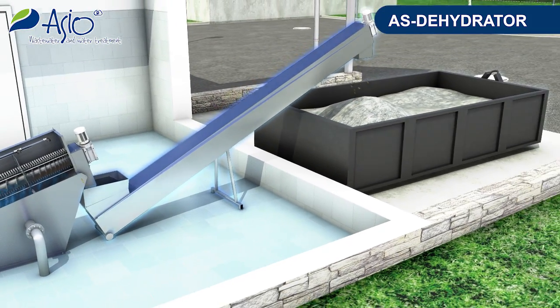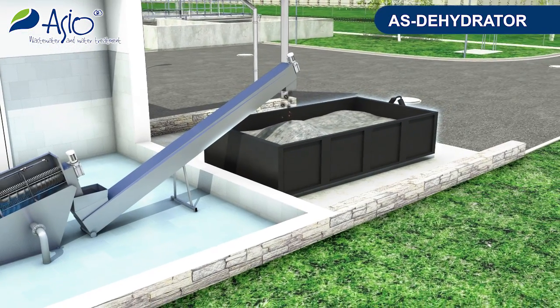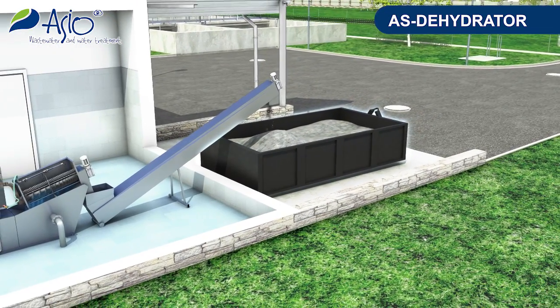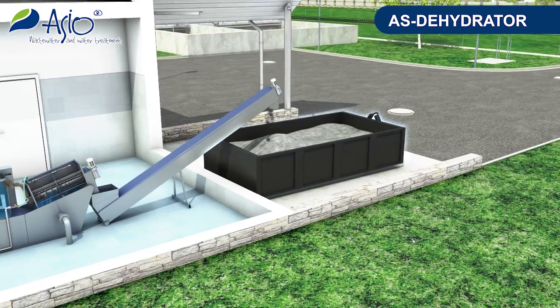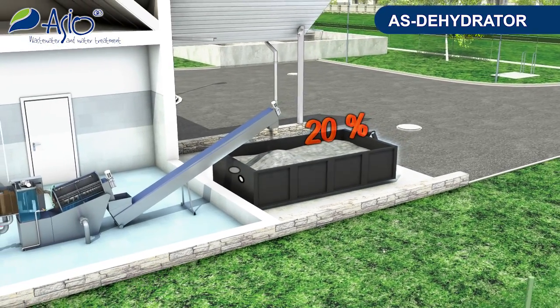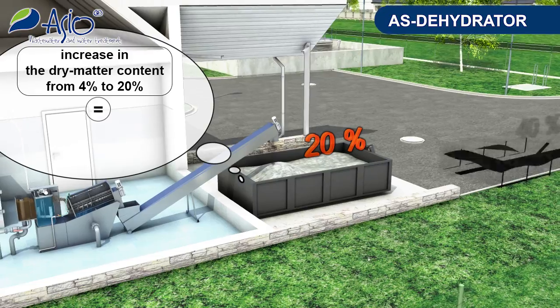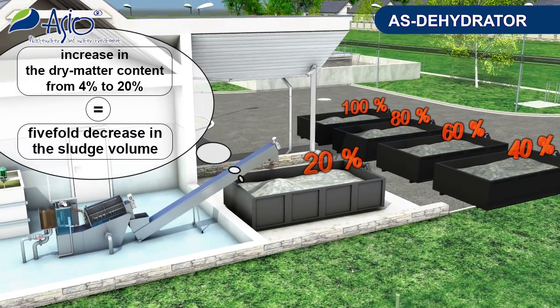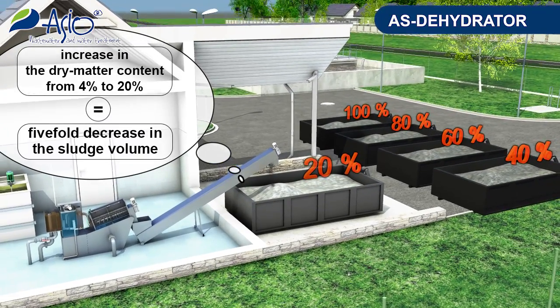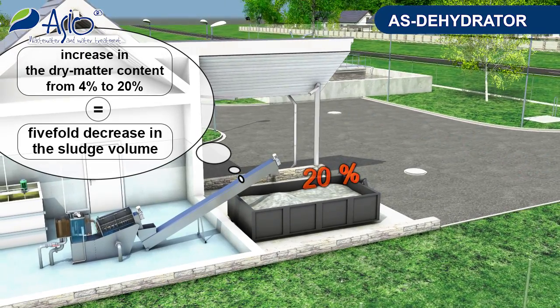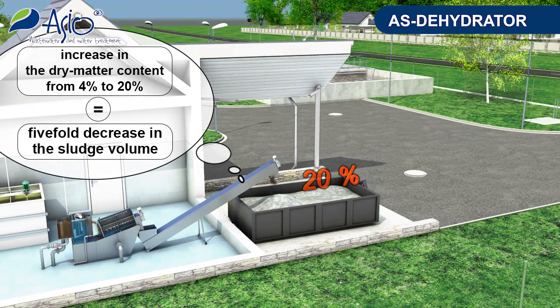The dewatered sludge is then usually placed into a container and can be used, for instance, in composting plants. It is worth noting that the increase in dry matter content from 4% to 20% represents a roughly five-fold decrease in sludge volume, resulting in a considerable reduction of transport and disposal costs.